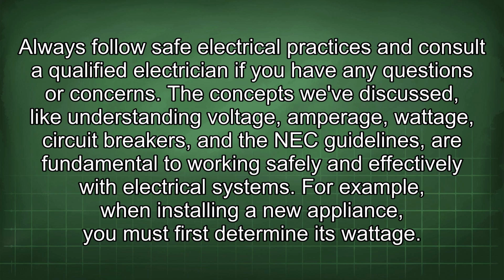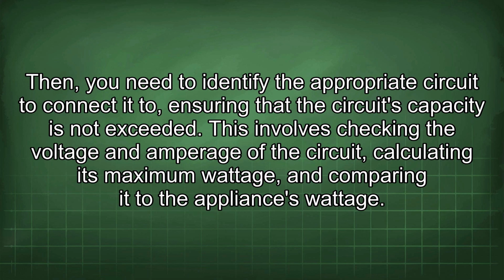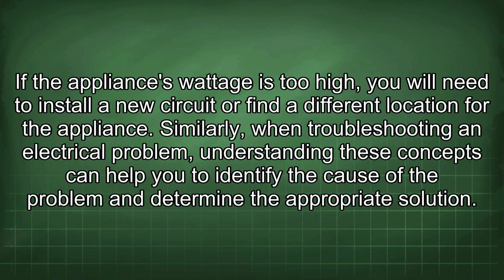The concepts we've discussed, like understanding voltage, amperage, wattage, circuit breakers, and the NEC guidelines, are fundamental to working safely and effectively with electrical systems. For example, when installing a new appliance, you must first determine its wattage. Then, you need to identify the appropriate circuit to connect it to, ensuring that the circuit's capacity is not exceeded. This involves checking the voltage and amperage of the circuit, calculating its maximum wattage, and comparing it to the appliance's wattage. If the appliance's wattage is too high, you will need to install a new circuit or find a different location for the appliance.